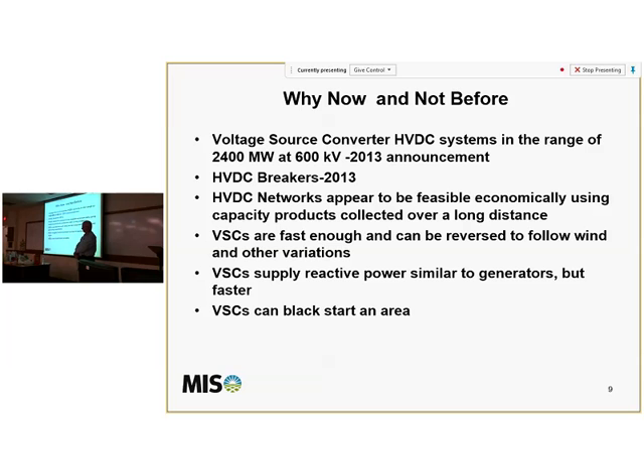The main thing that happens when you lose a big generator is you not only lose the power, but you lose all the reactive power from it, so you get a voltage drop in the area where you lost the generation. The DC can supply reactive power to give you voltage regulation, which makes the AC system work better, plus the DC power and reactive power. And when it's not running, it can be used for voltage support—putting 1,000 megavars of voltage support into an area is pretty good regulation.